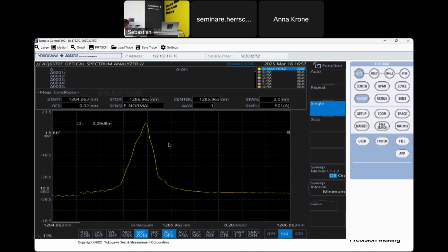And you see, this would really take a long time. To improve this, we have implemented the gate mode, and in this device also with the advanced gate mode settings, so that the measurement in the max hold function is not needed.